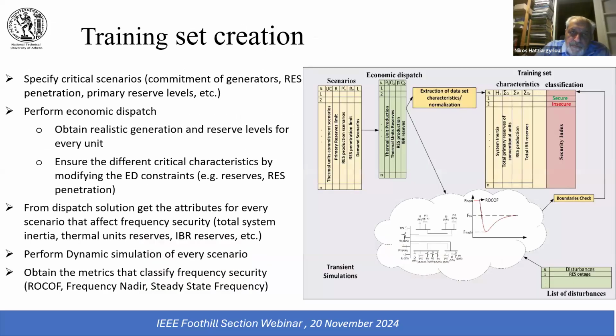So how this happens: you specify the critical scenarios — the commitment of generators, renewable penetration, primary reserve levels — what defines a critical scenario. You perform economic dispatch to obtain realistic generation and reserve levels. From the dispatch solution you get the attributes for every scenario that affect frequency security, perform dynamic simulation, and for each scenario obtain the metrics that classify frequency security: rate of change of frequency, frequency nadir, and steady state frequency. These are the values that define the frequency performance of each scenario based on detailed models of the power system.